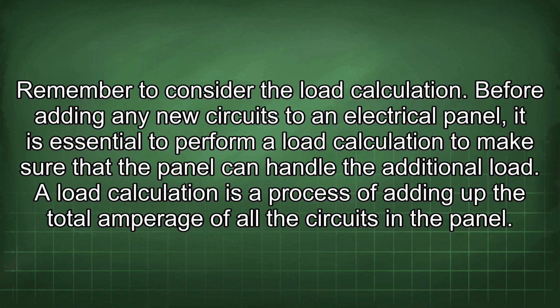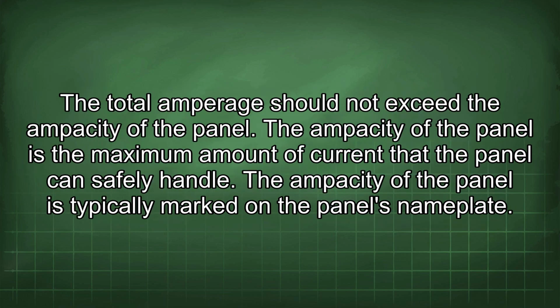Remember to consider the load calculation. Before adding any new circuits to an electrical panel, it is essential to perform a load calculation to make sure that the panel can handle the additional load. A load calculation is a process of adding up the total amperage of all the circuits in the panel. The total amperage should not exceed the ampacity of the panel. The ampacity of the panel is the maximum amount of current that the panel can safely handle. The ampacity of the panel is typically marked on the panel's nameplate.